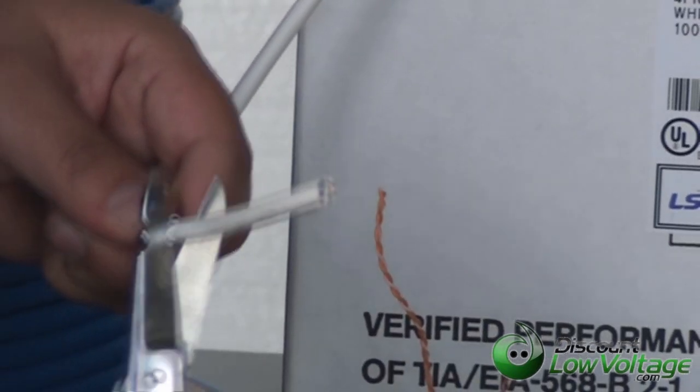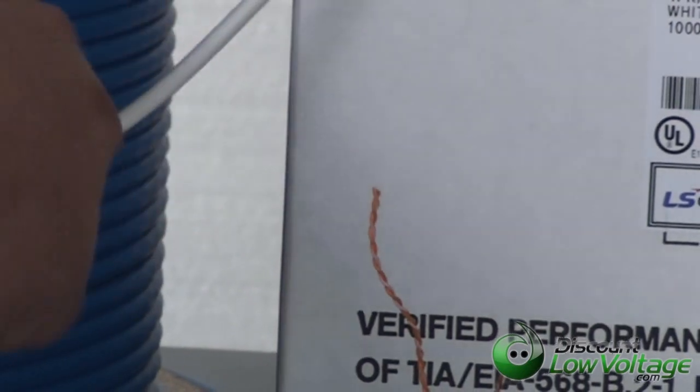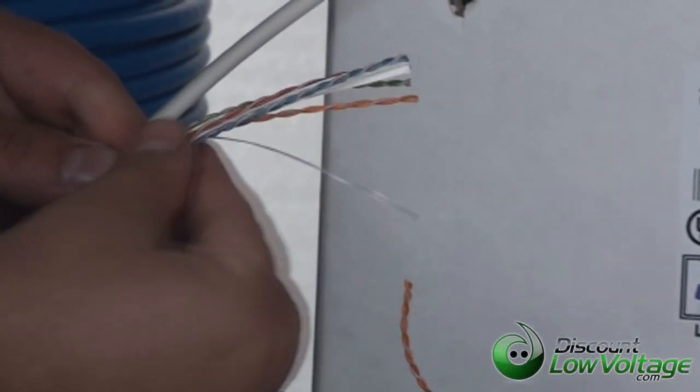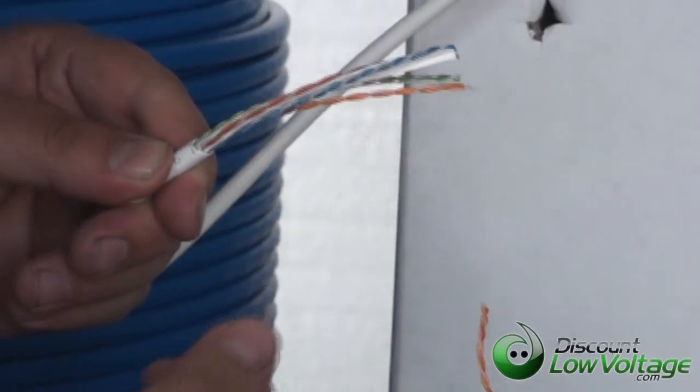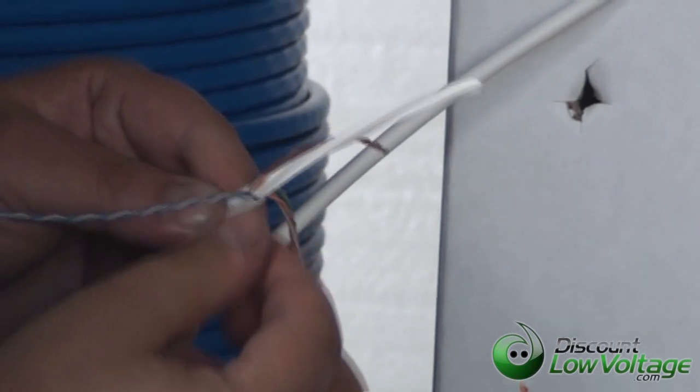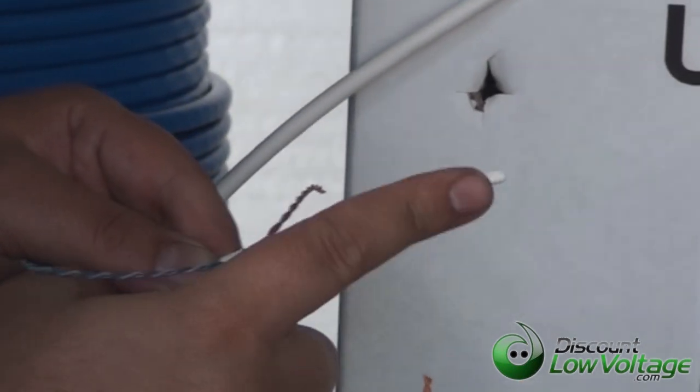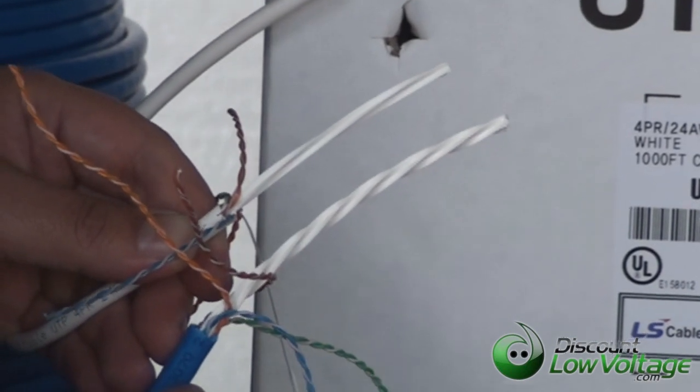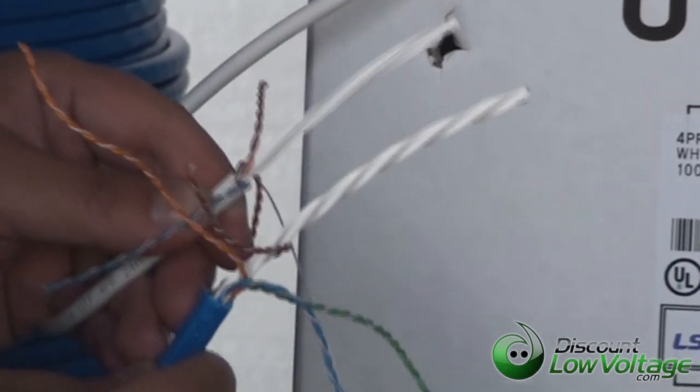Now Cat 6 supports speed of 10 gig up to 55 meters. So obviously the pairs aren't twisted around the center spline. They are twisted tighter than Category 5 and the center spline does have a little bit of a twist to it, but not as much as the Cat 6A.